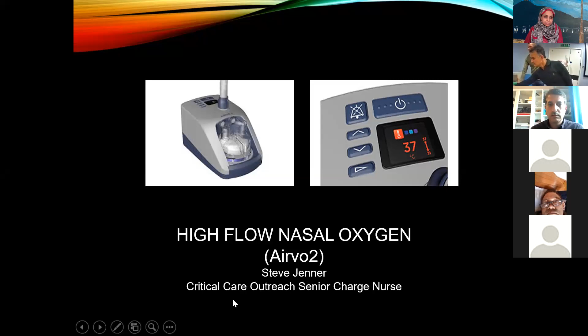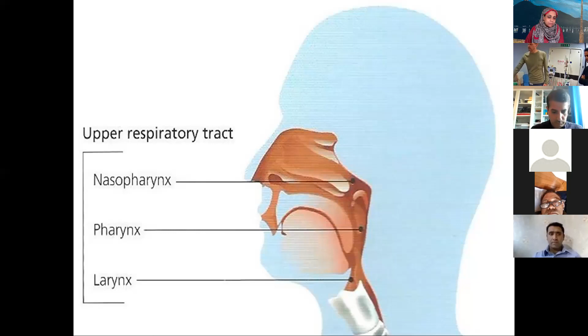Okay, so obviously it's driven by nasal cannula. It has several modes of function that have a positive impact on the patient's therapy and recovery. One of the primary modes is it provides a washout of what we call the anatomical dead space. The high flow rates, up to 60 litres a minute, help keep the anatomical dead space full of oxygen-rich air for each inspiratory phase of the breath cycle.